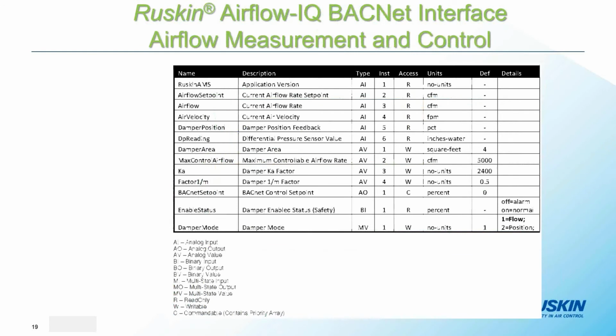As I mentioned, all of that information, these 12 data points, is what is now output dynamically onto the building automation system. So you're able to read these points and to command a CFM set point. You're able to toggle it from flow control to position control. And again, just a wealth of information that is coming right out of this actuator, including damper position, airflow measurement, air velocity. All of that is right here, and then you just simply command it via your automation system. Anyhow, really excited to be offering this product, air measurement and control, in one setup here.